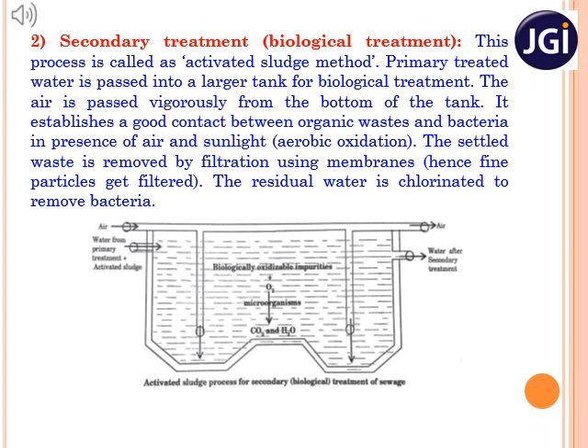By passing air, a good contact between organic waste and microorganisms is established in the tank, resulting in aerobic oxidation of the waste. The settled waste is removed by filtering through a membrane, which filters finer particles. The remaining water is treated with chlorine to remove bacteria. Since this step involves use of microorganisms, it is also called biological treatment.